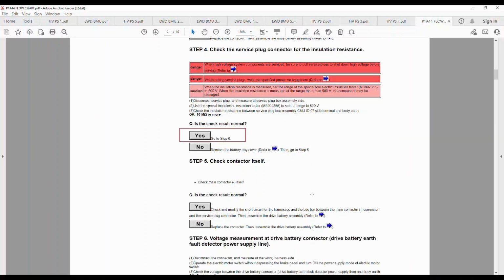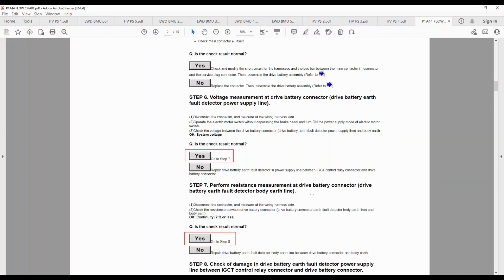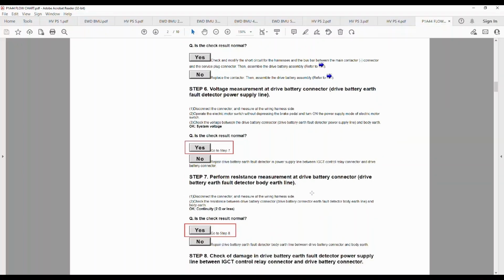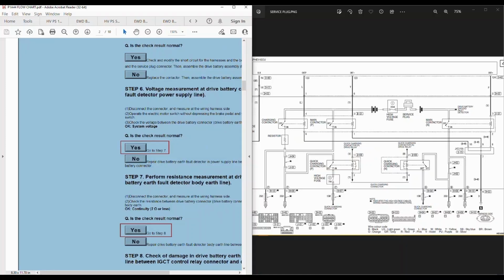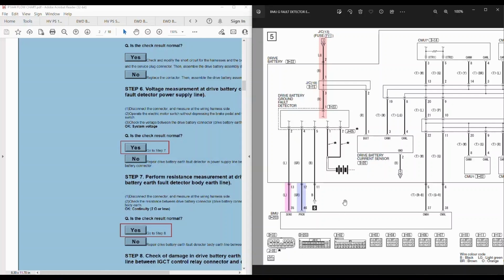So now we move on to step six. Now, this was voltage measurement at the battery, drive battery connector, drive battery earth fault detector power supply line. So again, disconnect the connector and measure at the wiring harness side. Operate the electric motor switch without depressing the brake pedal and turn on the power supply. And check the voltage. So again, let's get the wiring diagram up. It will make things much easier. So let me move this across here. And the diagram this time is this one here.